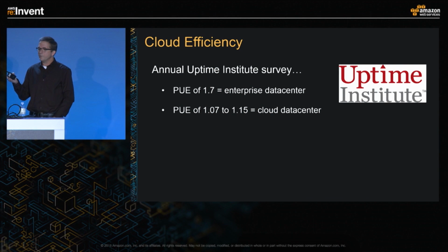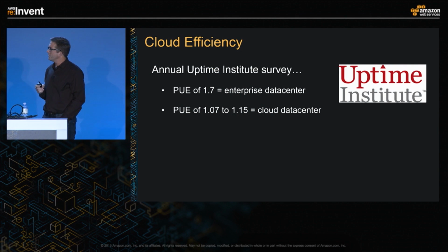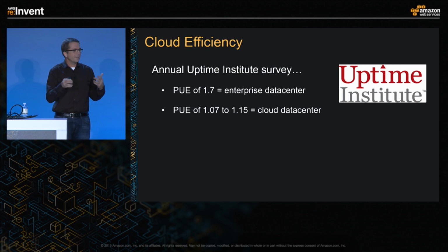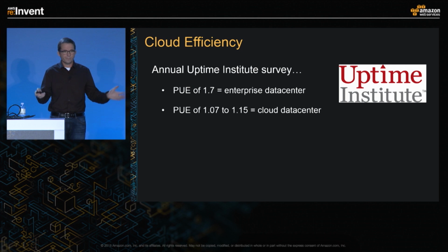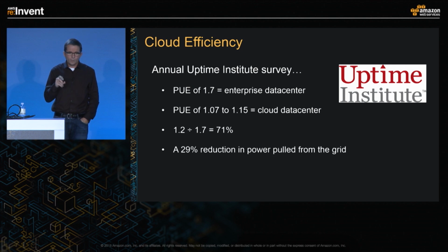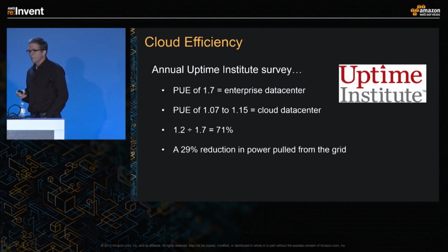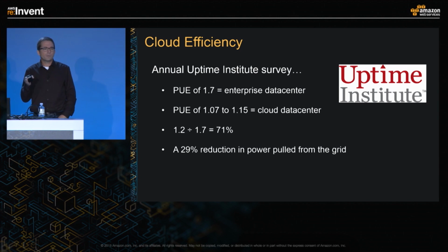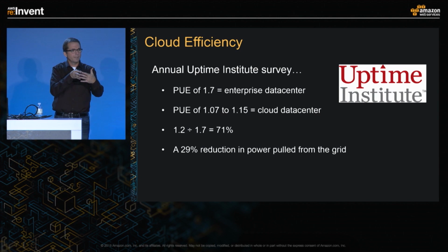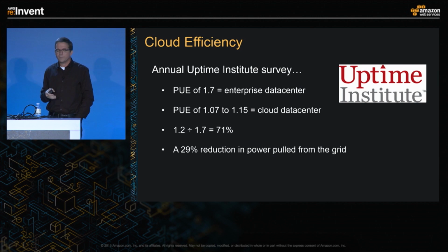And in the cloud data centers, they found a 1.07 to 1.15 PUE. Now, to simplify this calculation and to be a little conservative, I'm going to use 1.2 for this illustration. With 1.2, you use 71% of the power from the grid on the cloud than you would from an enterprise data center. That's a 29% reduction in power that you need from the grid.